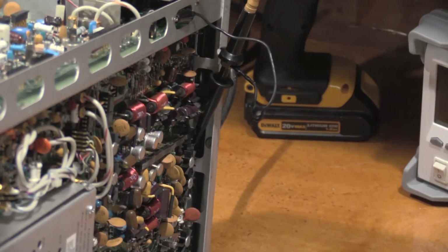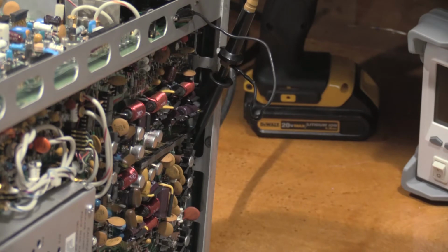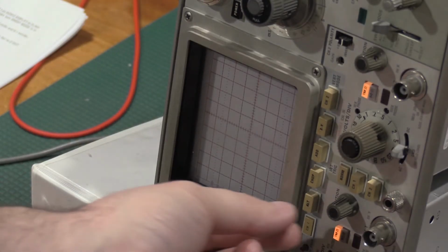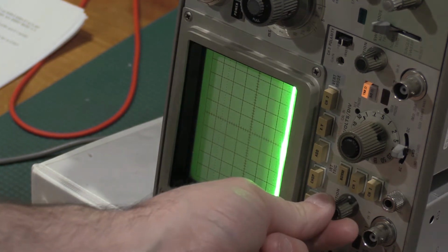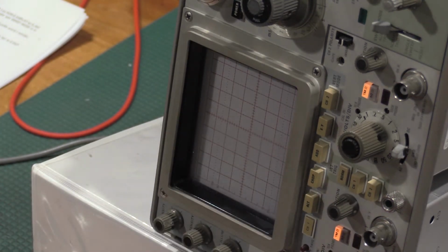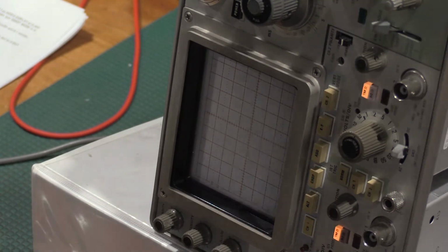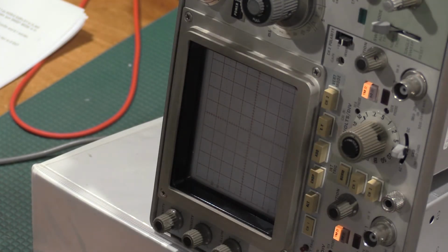All right, we've got a test probe hooked up to the high-frequency output of the Z out. We need to look for how good the square wave is. And we also need to look for rise time. So I'm going to get the Rigol set up, get it triggering, and then we'll take a look. You'll want to position this off the tube because it's really bright, so I zip it off down the side to take a look. Let us take a look at what we've got.